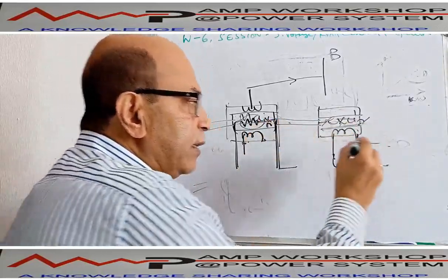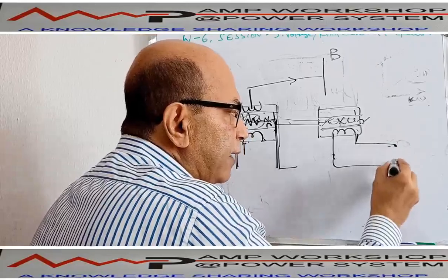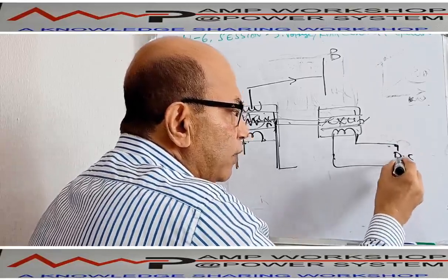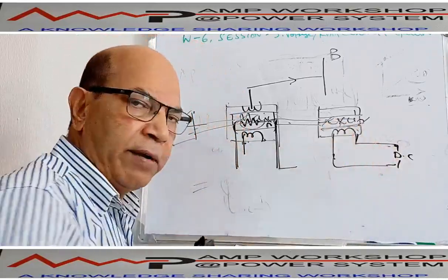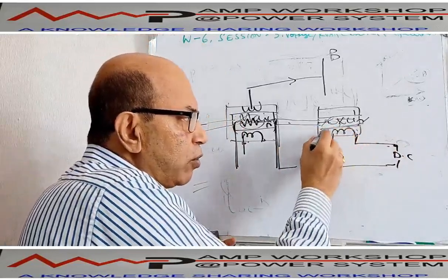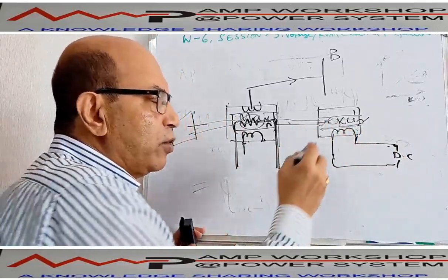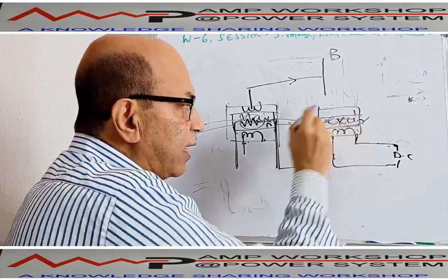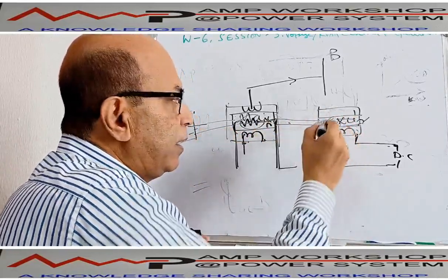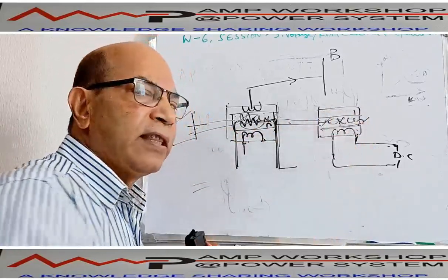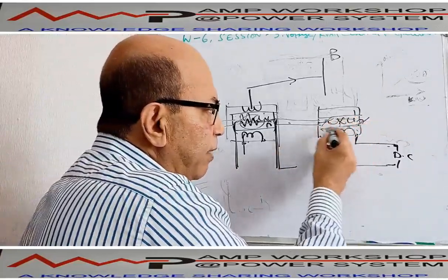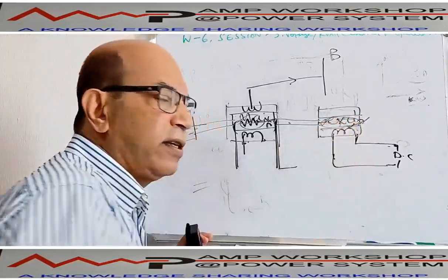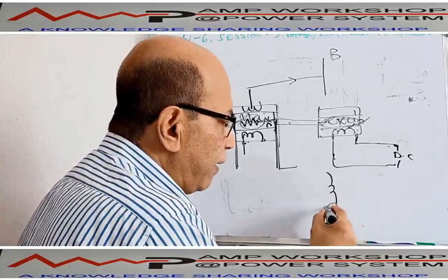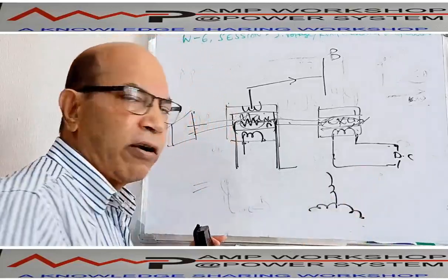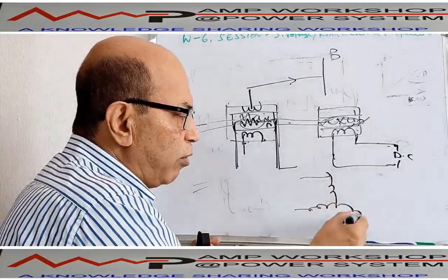The field is fixed. This field is getting excitation from the DC source. So this field could be a permanent magnet, or it could be an electromagnet. When it is magnetized and this exciter is rotating with the turbine, it is producing three phases here. This armature winding or stator winding is a three phase winding, connected in delta or star. So it is producing three phase voltage.